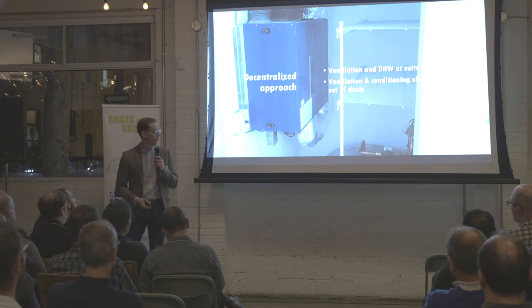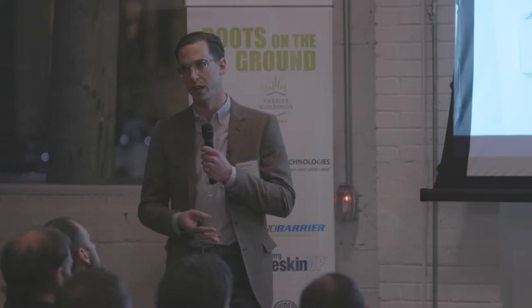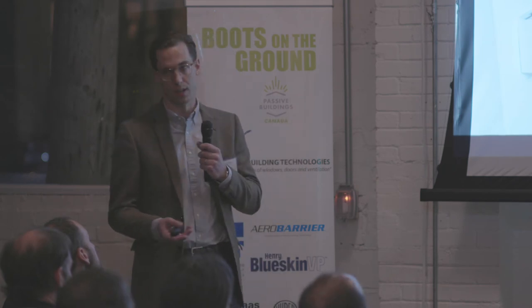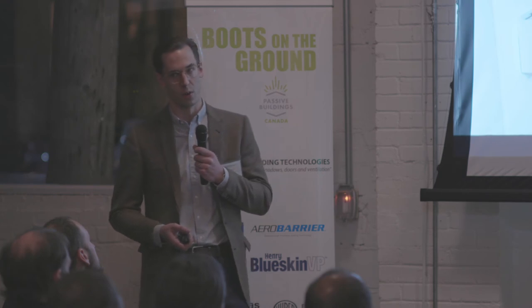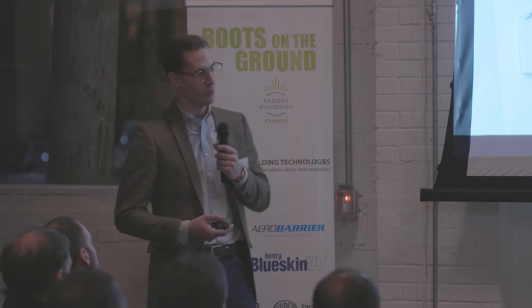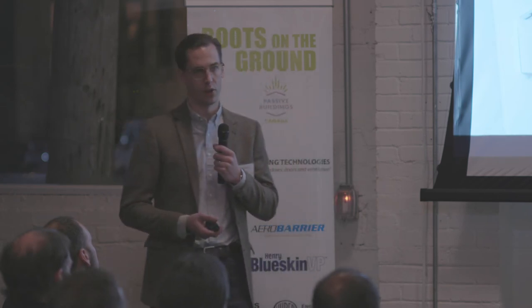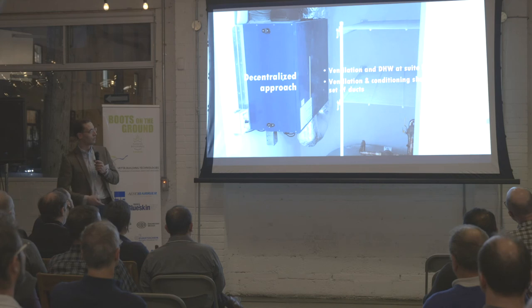On the HVAC and hot water side, one of the first questions we usually ask is: who's paying the utility bills? If it's on the house, we can use different strategies than if it's on the tenants. In this case it was on the house — tenants were not paying — so we could have gone to a centralized system, and had we been involved from the very beginning we probably would have. But because of the building geometry, it wasn't easy to do that on the ventilation side, and we didn't have enough space for hot water. So we're locked into one electric tank in every suite, and it's not practical to put a heat pump water heater in a 500-square-foot apartment. We went to a decentralized, compartmentalized ventilation system.